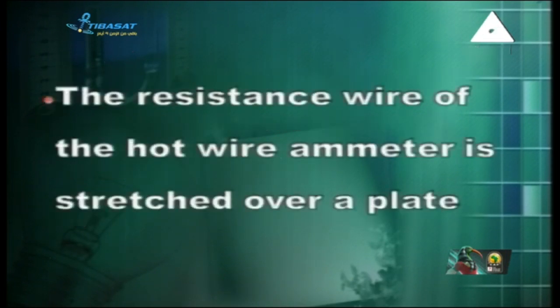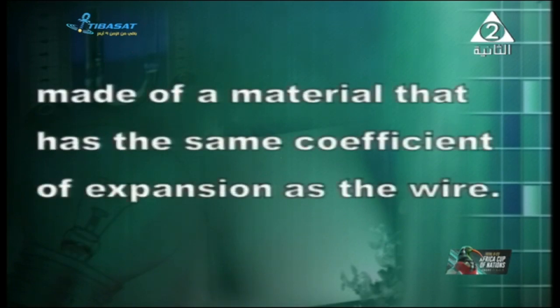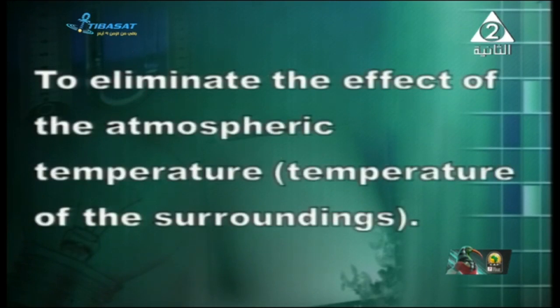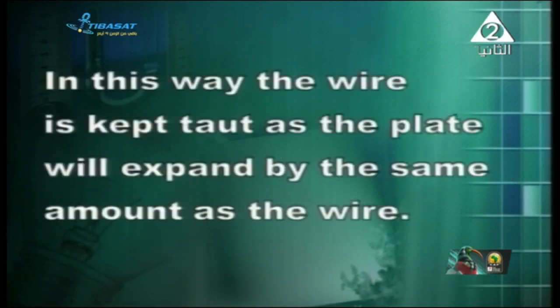Another give reason: the resistance wire of the hot wire ammeter is stretched over a plate made of a material that has the same coefficient of expansion as the wire. This is to eliminate the effect of the atmospheric temperature of the surroundings. In this way, the wire is kept taut, as the plate will expand by the same amount as the wire.